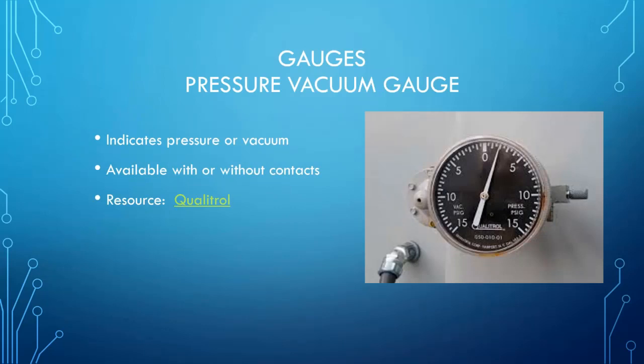Of course, it indicates liquid-filled transformers are sealed devices. They are not meant to exchange air with the outside world. So a pressure vacuum gauge is a very helpful device for a maintenance person to check quarterly or annually. And you really want to look for any value other than zero. The one shown in this picture has the best reading you can hope for, which is a positive pressure, which means, A, that the transformer is still sealed. It hasn't lost its integrity. The tank has not been compromised.